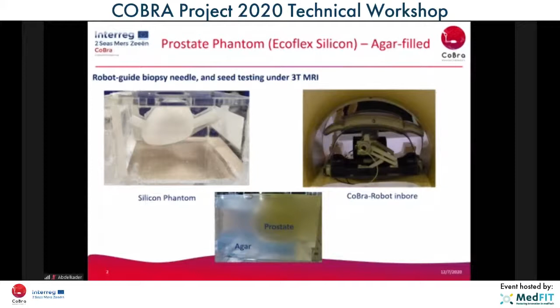In this case, we developed the silicon phantom with the colleagues that you see on the top left. We stabilize the external volume of the phantom with agar-agar material. The feedback of the MR images are shown here in these 4 pictures with the different views, where we can see that the piezo-sonic ultrasound motor used to guide the 5 degrees of freedom and the Heidenhain absolute encoders do not give any artifact in-bore MR.